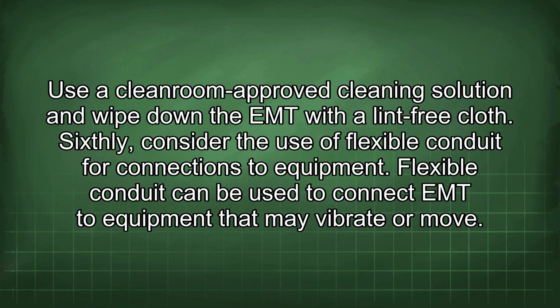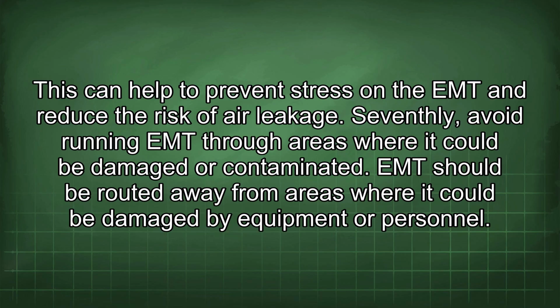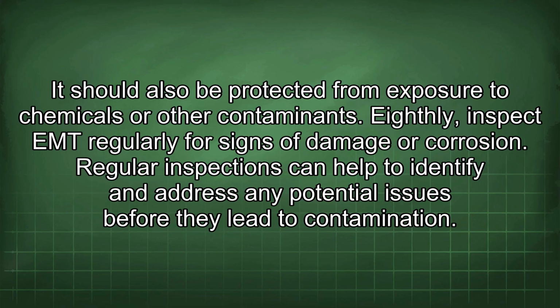Sixthly, consider the use of flexible conduit for connections to equipment. Flexible conduit can be used to connect EMT to equipment that may vibrate or move. This can help to prevent stress on the EMT and reduce the risk of air leakage. Seventhly, avoid running EMT through areas where it could be damaged or contaminated. EMT should be routed away from areas where it could be damaged by equipment or personnel. It should also be protected from exposure to chemicals or other contaminants.